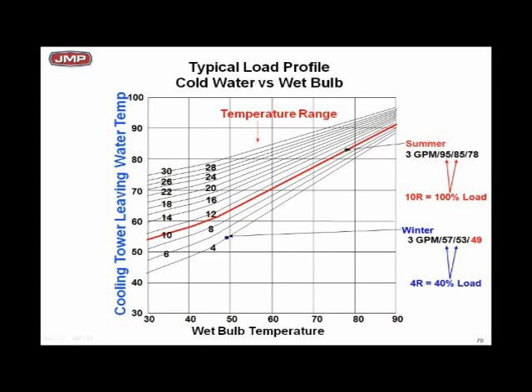Real simple. How cold of water can you make? How much of it? Well, with 10-degree range, I'm saying I got a constant load on my tower. The reason I'm doing that so you can grasp what's going to happen here is I lower the wet bulb temperature. Real basic, simple statement. Cold air holds less moisture. Cold air holds less moisture. A cooling tower is an evaporation machine. A cooling tower evaporates water.